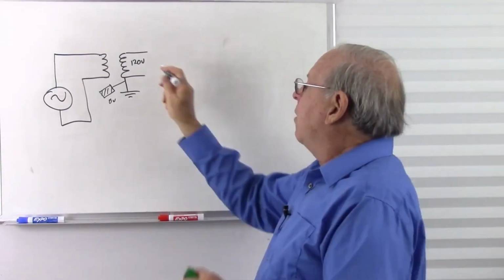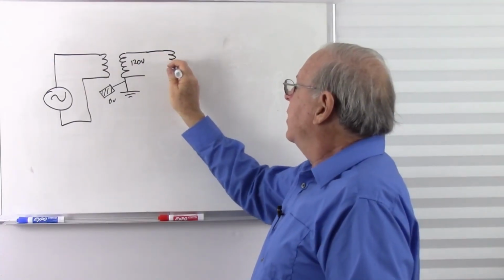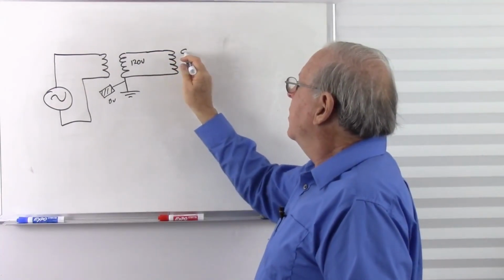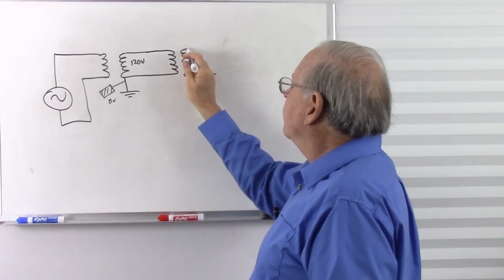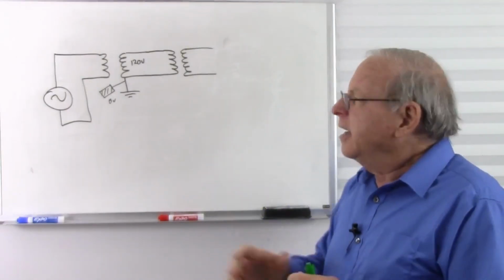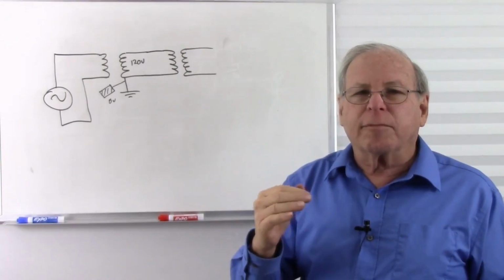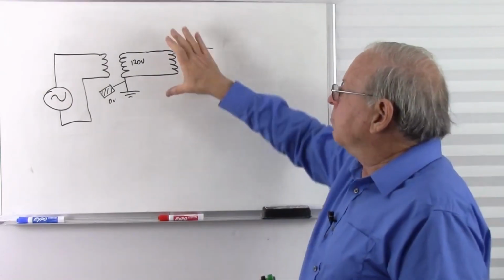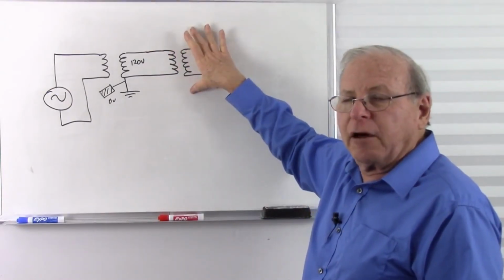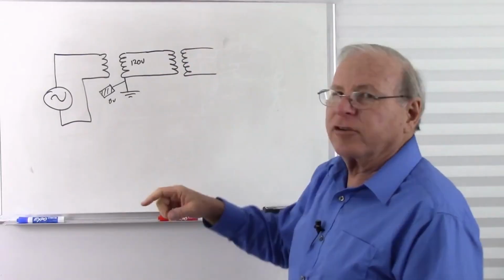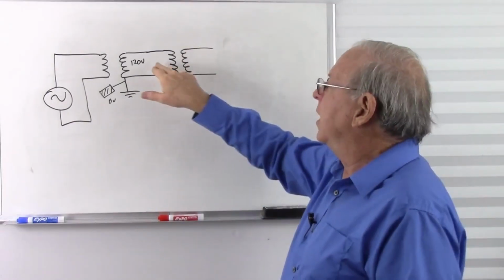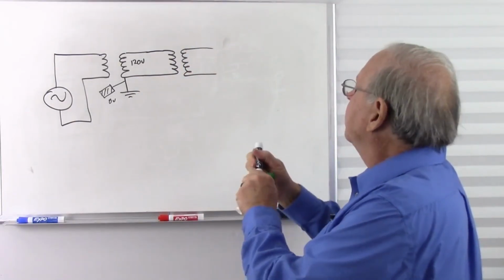So we come out of the wall. We'll assume that wall connection is right here. Here's our isolation transformer. In this case, it'll be just a 1-to-1 transformer. They often are. Now, isolation transformers might be tapped in a way that we can have multiple input voltages and multiple output voltages, but the classical isolation transformer is a 1-to-1, so 120 volts in, 120 volts out.